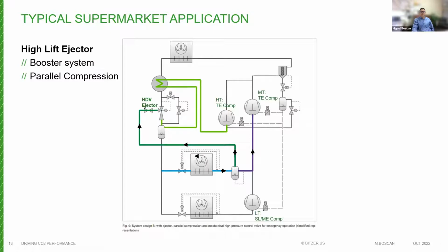The mass flow being diverted from the medium temp compressors to the high temp compressors is processed at a lower pressure ratio, and therefore at a more efficient operating point. So that's the goal of the ejector: to divert the mass flow from a less advantageous pressure ratio to a more advantageous pressure ratio, using the parallel compression that is already a rather common design feature of a CO2 rack.